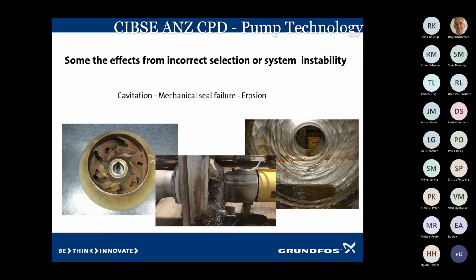The one in the middle, I took a photo of that. I thought that was quite good. That's a mechanical seal leaking. When I went into the plant room, they had a yellow coat over the top to stop the water getting out all around the plant room, and there was a mechanical seal leaking away. So the best way they thought to fix that was cover it up. That's not a good one.